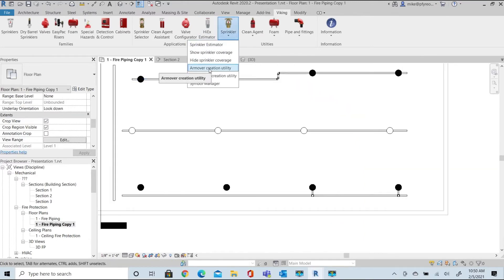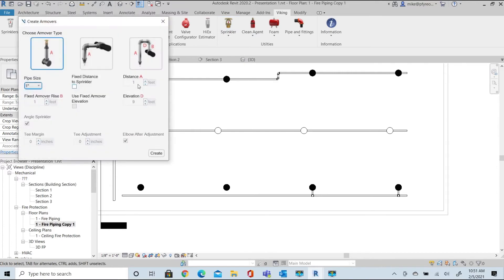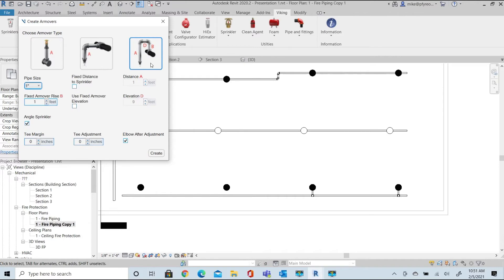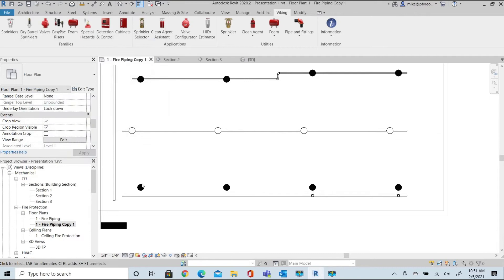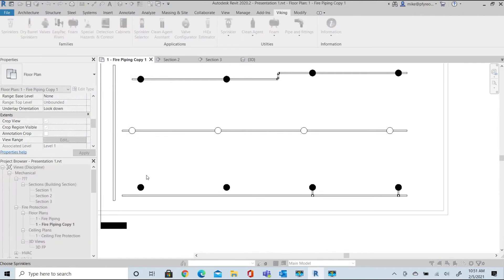Next, let's select the return bend option. With the return bend option, you can set the riser nipple length or the arm over elevation. The result is the center to center length of the riser nipple. Let's set the riser nipple length to 6 inches. Notice that the dimensions are in decimal feet. Select the head, then select the branch line, and look at the 3D result.